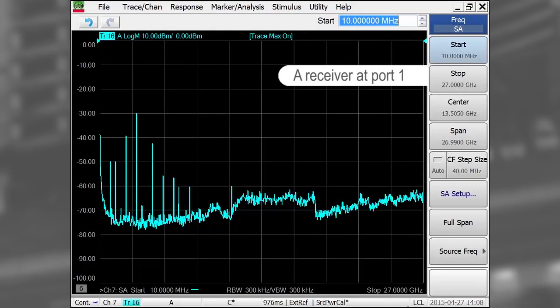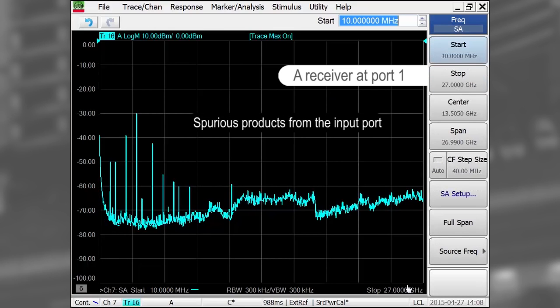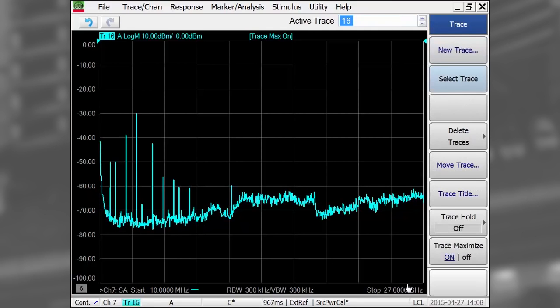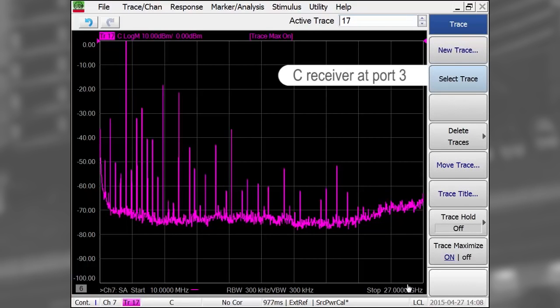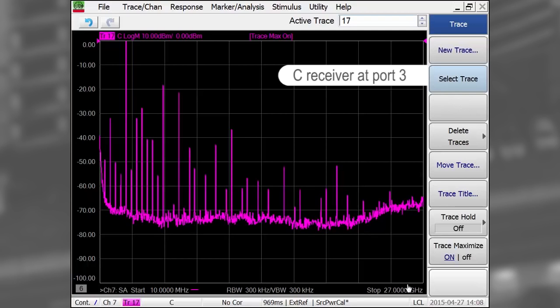The A receiver at port 1 shows the spurious signals coming out of the input port, which, if connected to an antenna, could cause radio frequency interference. The C receiver at port 3 shows the large amount of spurious products coming out of the converter's LO port, which, in this case, is to be expected since there are no LO amplifiers to provide reverse isolation.